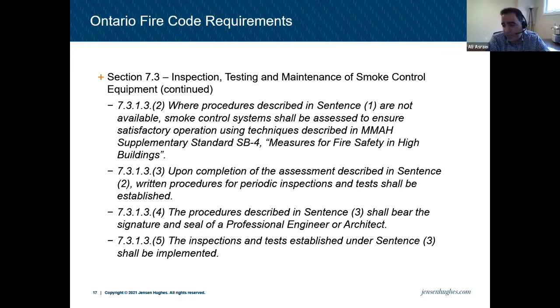Okay. And sentence 4 says that the procedure described in sentence 3 shall bear the signature and seal of a professional engineer or an architect. So what it says is that if you don't have the original test and maintenance procedure provided by the designer of the system, you need to involve another engineer to do an assessment of the system and put together a procedure, stamp it, and give it to you. So moving forward, the owner can follow that procedure to maintain the system.